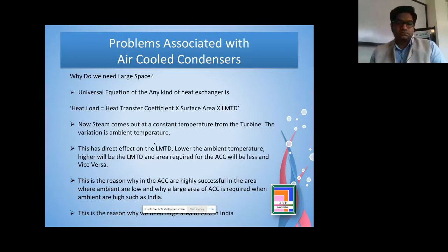So this affects the LMTD. When we have a lower ambient temperature, this LMTD goes higher. When this goes higher, our heat transfer area is sufficient, because the heat transfer coefficient depends on three things. One is the velocity of steam inside the heat exchanger. B is the airflow velocity on the outside of the heat exchanger, and C is basically the metallurgy, and what kind of fin tube arrangement we are using. So there is a constant U factor.